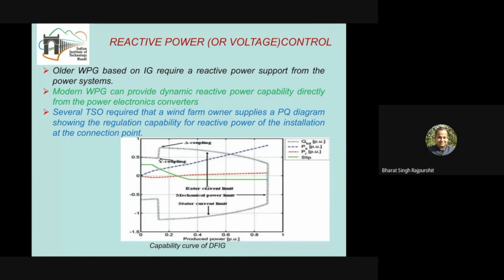Now the next requirement is that a capability curve of the induction machine, or any renewable energy technology, should also be provided to the transmission system operator, TSO. We are aware that no such capability curve existed a couple of years ago for an induction machine. But as I mentioned, the DFIG is able to generate and absorb reactive power by utilizing the power electronic converter. So some researchers came up with a curve known as the capability curve for the DFIG. Earlier, this type of curve was only available for the synchronous machine, but now it is available for DFIG-based induction machine systems also. These curves are required by the transmission system operator to understand how much limit is available with each wind farm for further provision of reactive and active power. So these are very important curves for understanding the current situation and the future requirements.